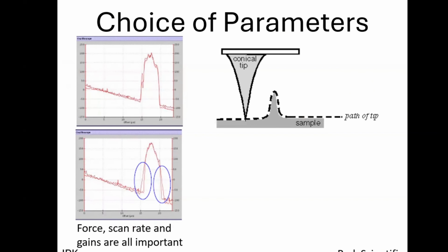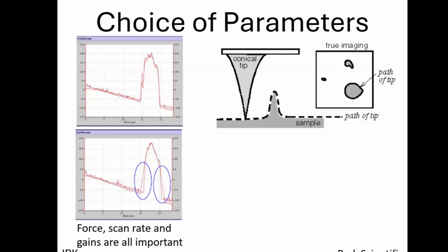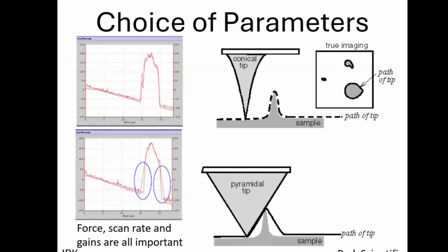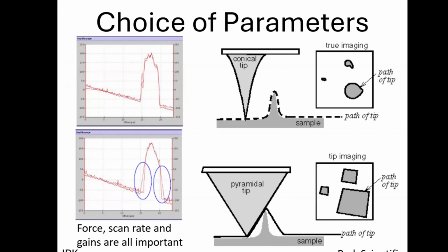Choice of tip is also critically important. The shape and aspect ratio can be important considerations. As shown here, a sharp tip accurately follows a surface compared to a blunt tip. This is a type of tip convolution or tip imaging, and is something you have to be careful with when collecting data. Sometimes your tip will break into a double tip, or you will pick up contamination on your tip. All of the surface features will now look like your double tip or your contamination.